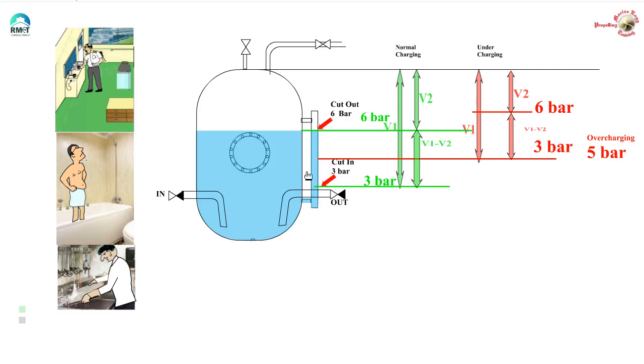Having a look here, that means when the water gets used up, the water is going to fall and when it reaches this level, which is just above the bottom of the gauge glass, the pump is going to cut in again because the cutting pressure is set at three bar. And what else we understand from this? The volume of water here between the cutting pressure and the cutout pressure is actually the volume of water which has been pumped out for one cycle of the hydrophore pump cutting in and cutting out. So V1 minus V2 is the amount of water the pump has pumped out before it cuts in again.